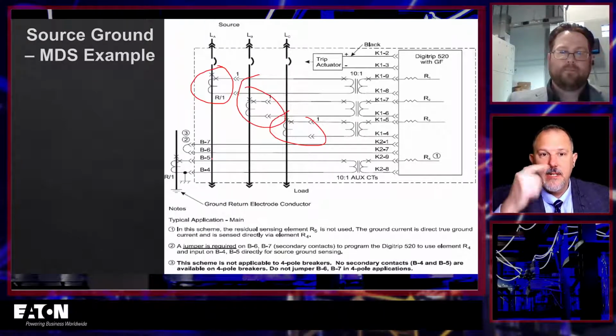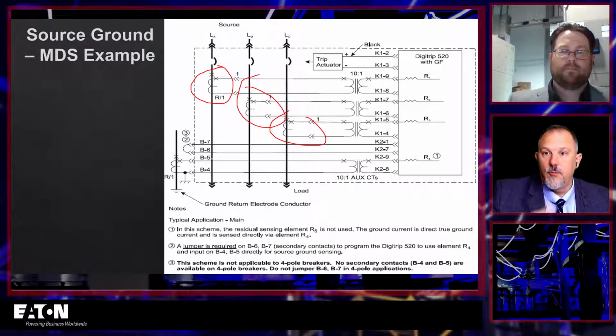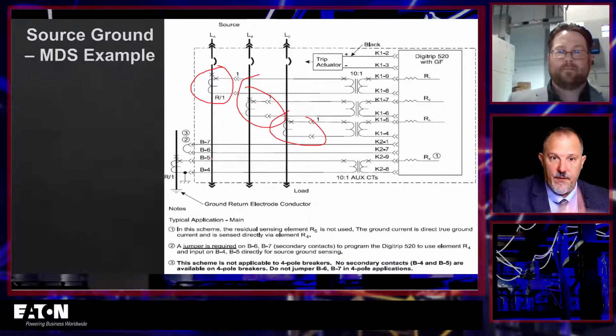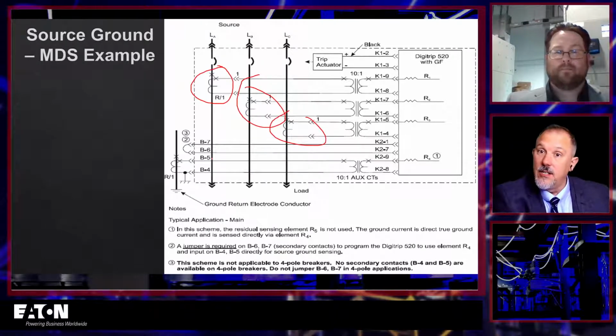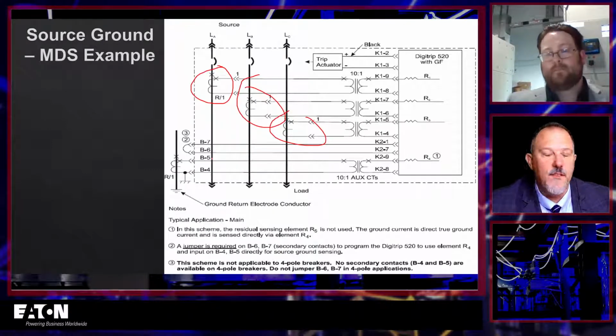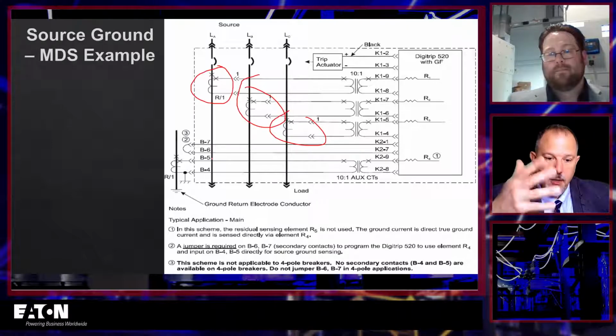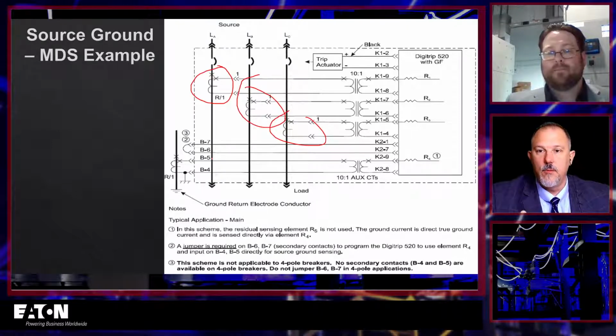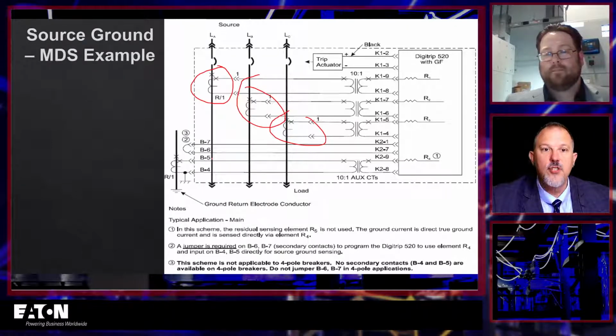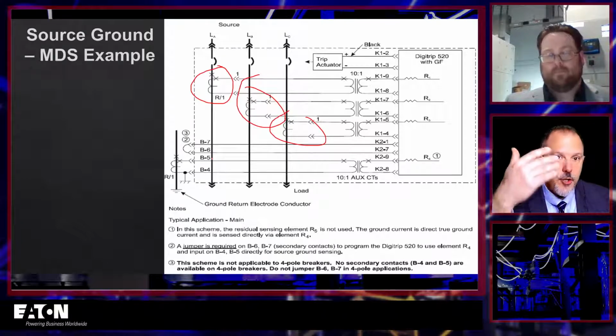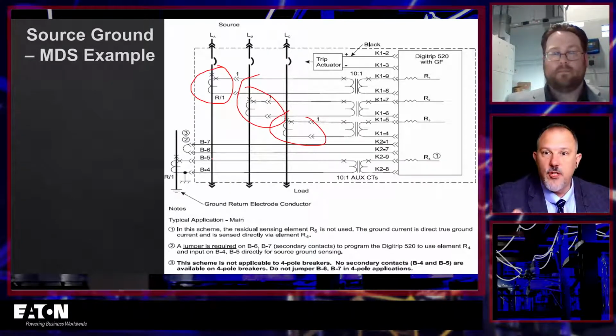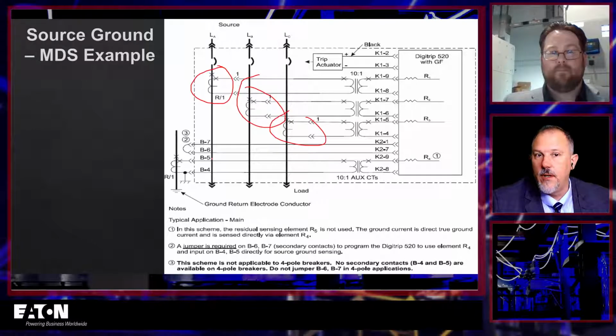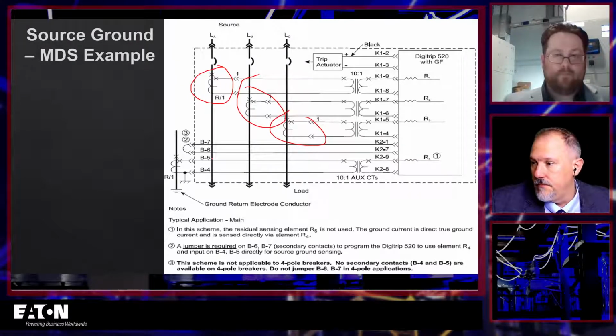But testing those sensors, because we'll do the standard testing just to make sure, you'll do a phase A, B, and C test in addition to the ground fault protection, because you want to kill all those birds with the same stone. If you're bringing the Phoenix out, use it and run the test through. You have a very low voltage pushing current, you can push enough to trip each one of these poles and test each one of those to make sure that everything is working correctly. Just do it.